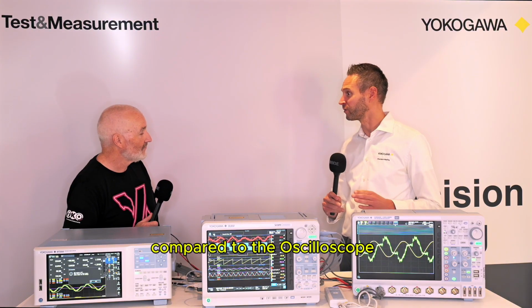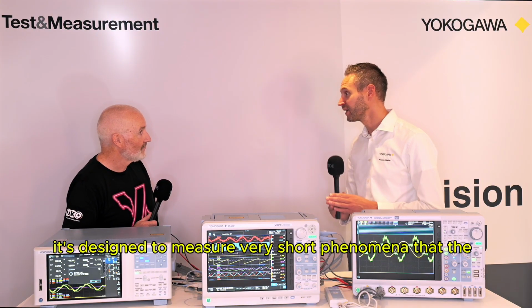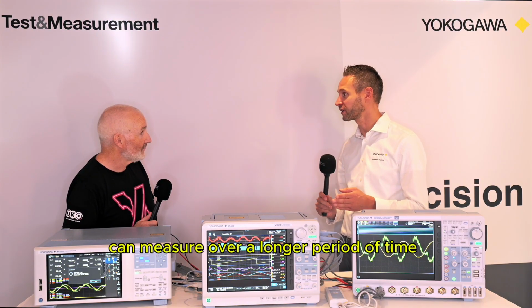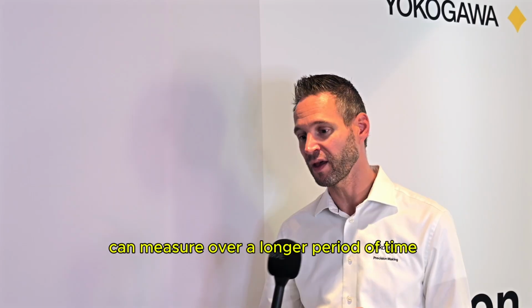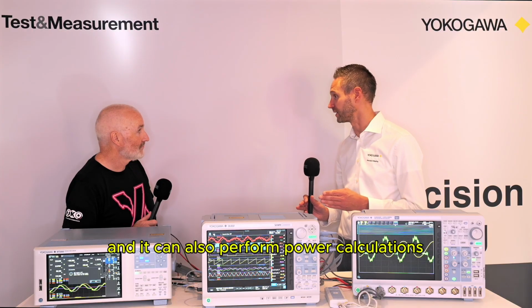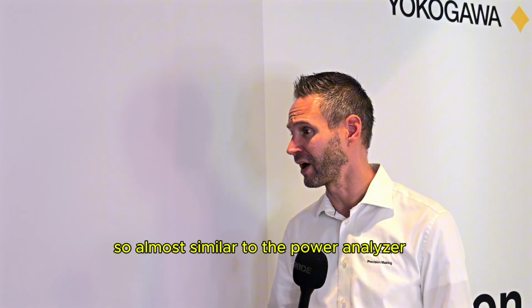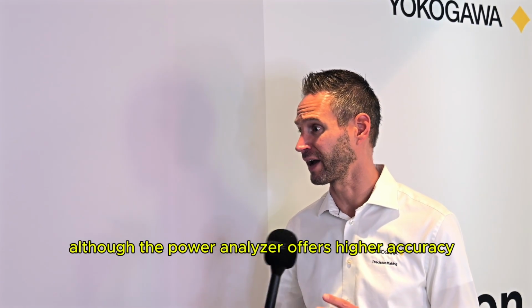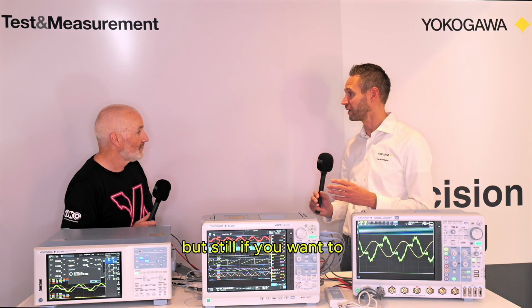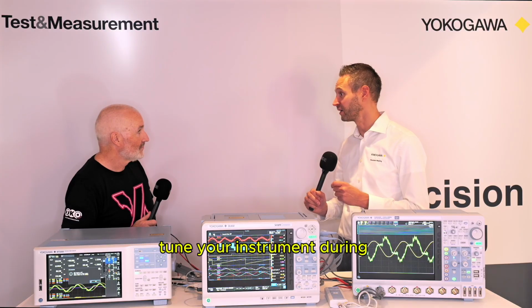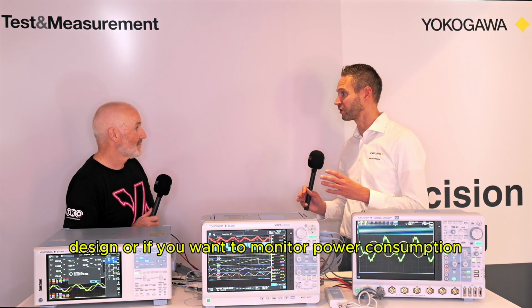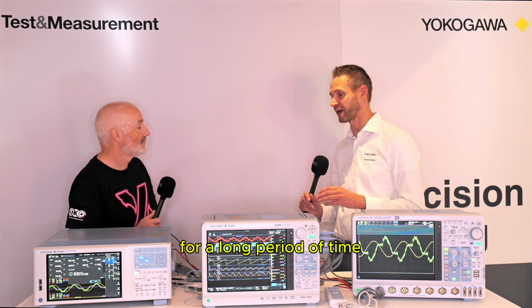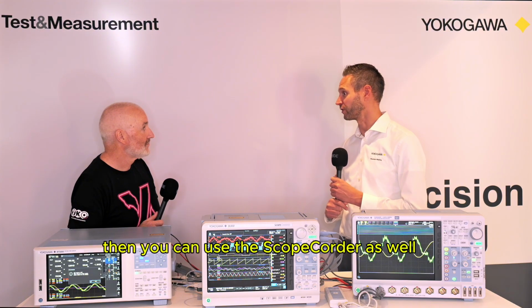Compared to the oscilloscope, which is designed to measure very short phenomena, the DL950 ScopeCorder can measure over a longer period of time. And it can also perform power calculations. So almost similar to the power analyzer, although the power analyzer offers high accuracy. But still, if you want to tune your instrument during design, or if you want to monitor power consumption over a long period of time, then you can use the ScopeCorder as well.